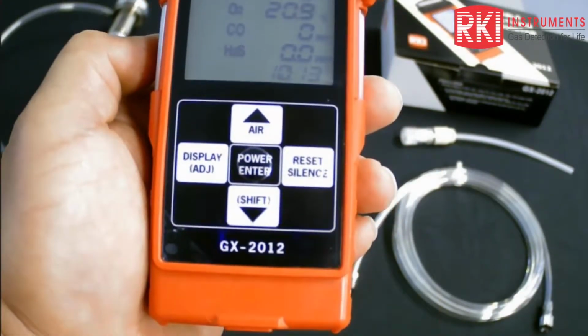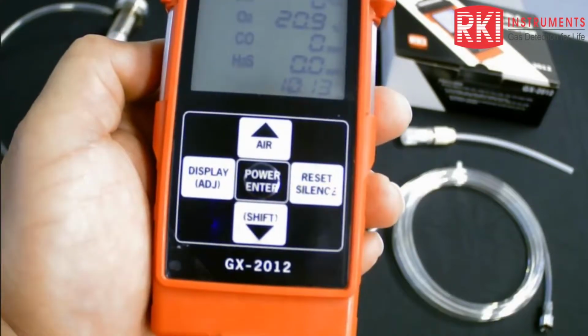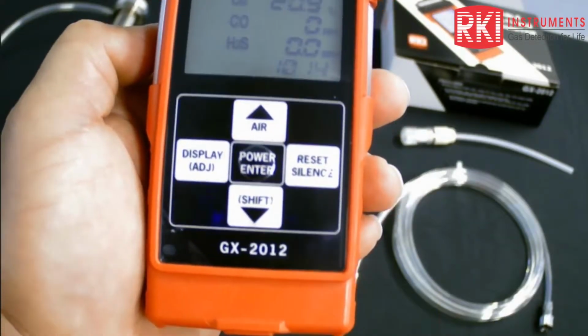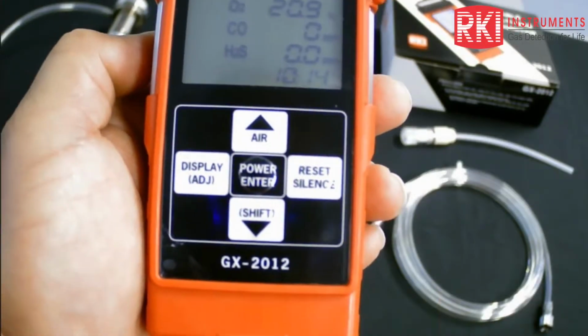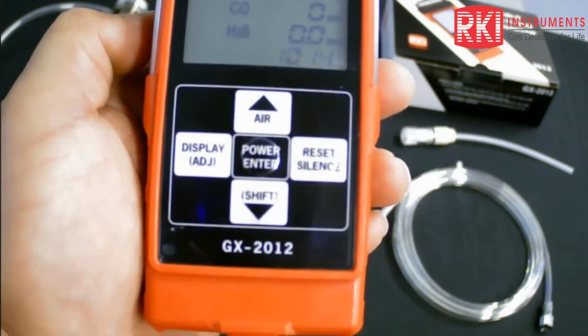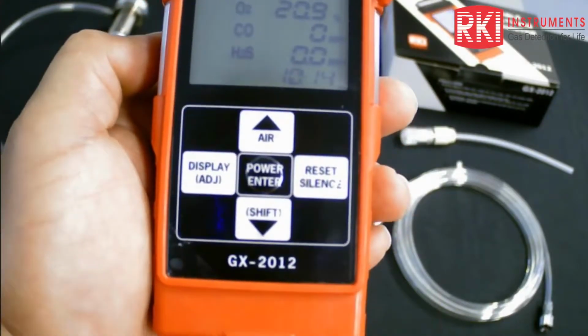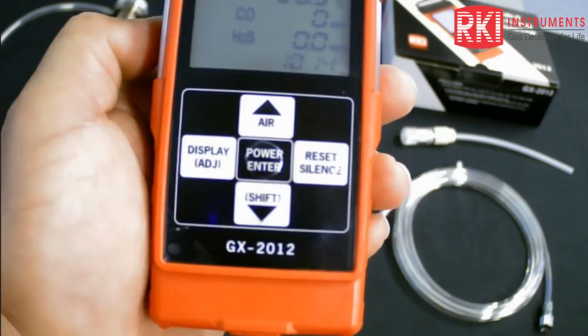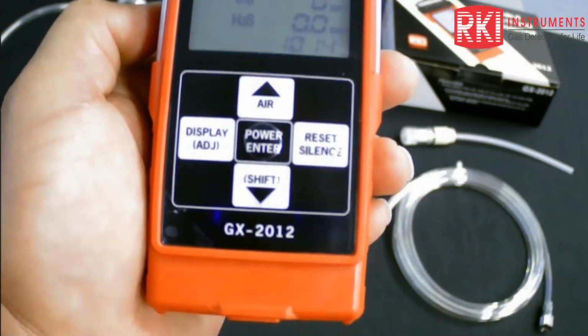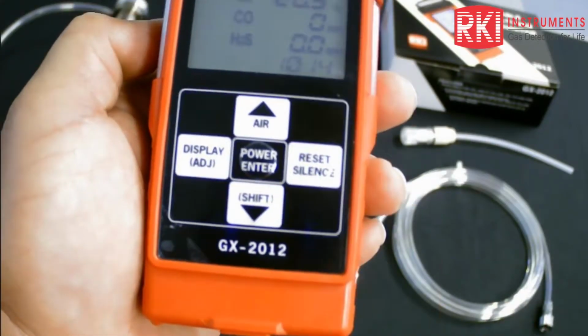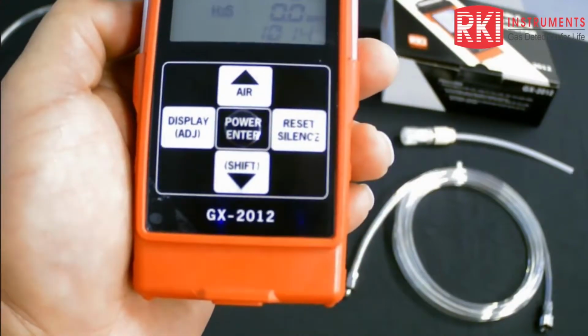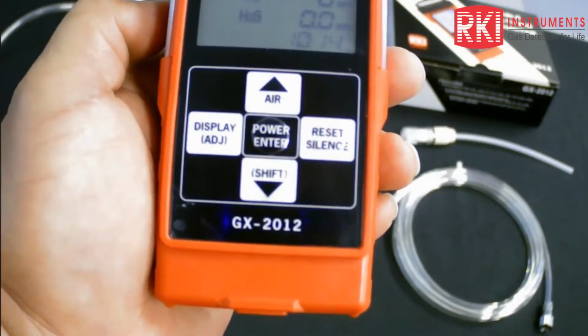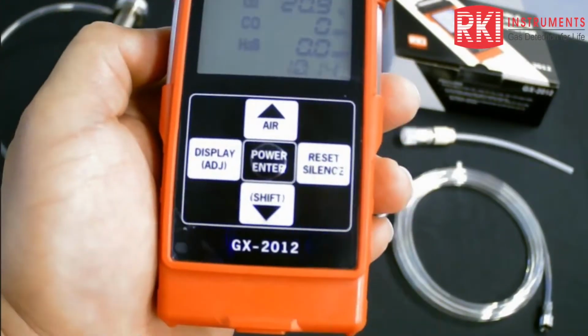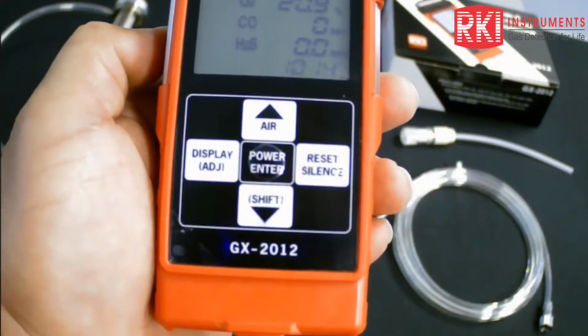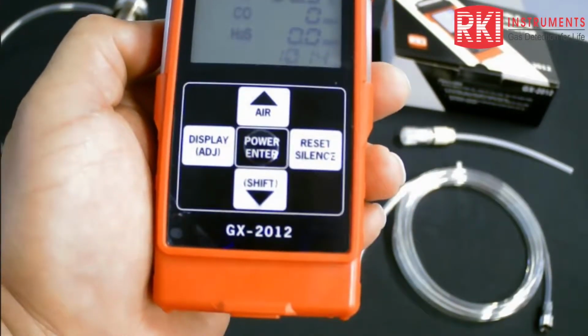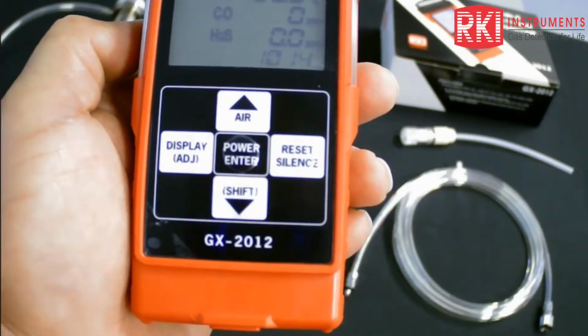So to safely measure the LEL, we have to put a catalyst there to enable that measurement at way below the explosive or flammable levels. In this case, you'd be able to see readings at 1%, 2% LEL, so quite a bit below, obviously, 100% LEL, and that's the purpose of the catalytic coating. So in the presence of frequent gas exposures or high concentrations of gas, that catalytic coating oxidizes away and the sensor becomes desensitized over time.